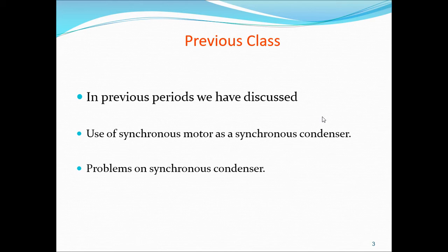So an overexcited synchronous motor draws leading current. So the system power factor can be improved by using a synchronous motor with overexcitation. A synchronous condenser is nothing but a synchronous motor operating without mechanical load but with strong DC excitation, that is overexcitation. Then the motor takes a leading power factor.